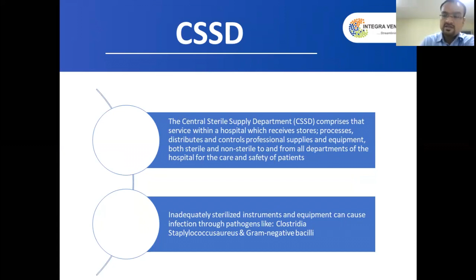So we need to have this nearby to the operation theatre, because the dependency of the operation theatre is maximum on CSSD, though CSSD is also required by other departments. It will also be adjacent to the service lift or the dumb waiters if not located on the same floor as the operation theatre. The standard space allocation for a 100-bed facility is approximately 700 square feet. There are different areas in the CSSD: packaging, storage, and dispatch, and proper zoning and proper flow need to be maintained.